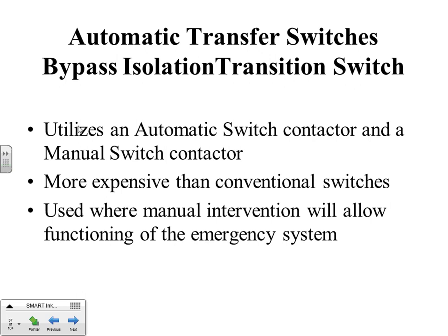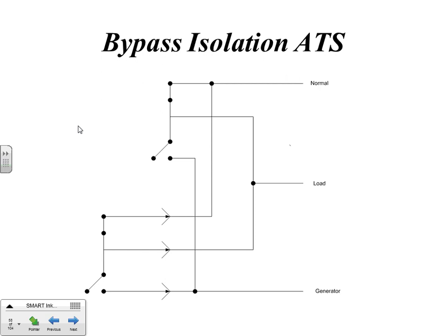I'll show that on the schematic here in a second. Because it has two contactors, it's going to be more expensive, obviously, than a conventional switch that has one. And it's used where manual intervention will allow functioning of the emergency system. A little more complicated in its design, but basically you've got two sets of contactors here. And notice that in either case, they're both connected to normal, this way and this way.